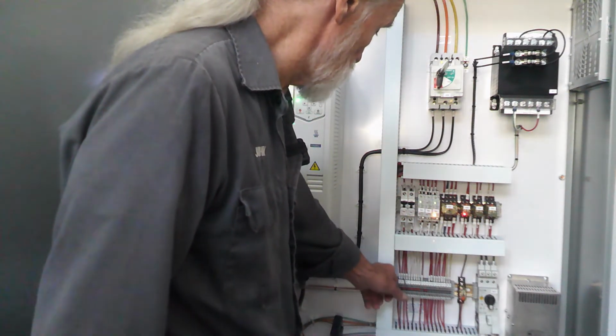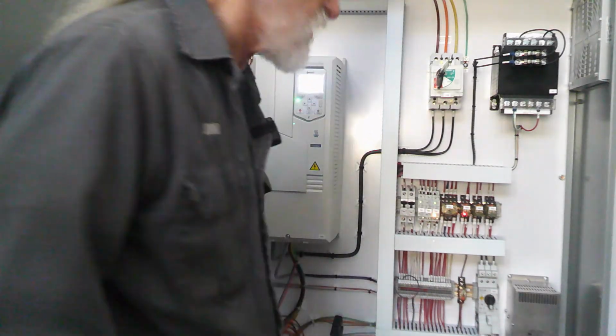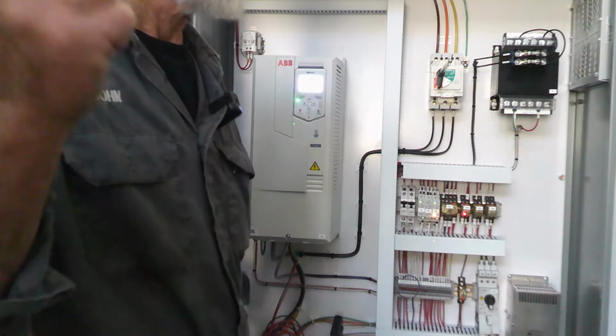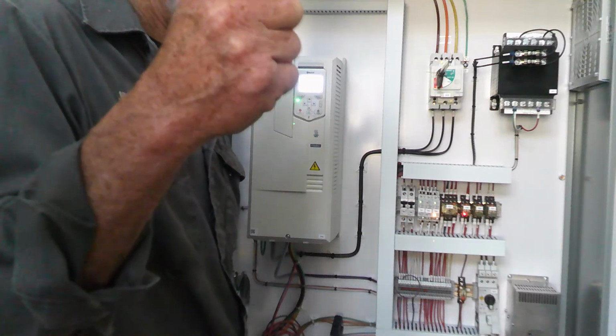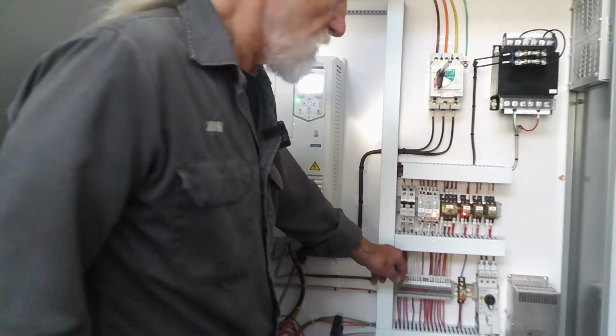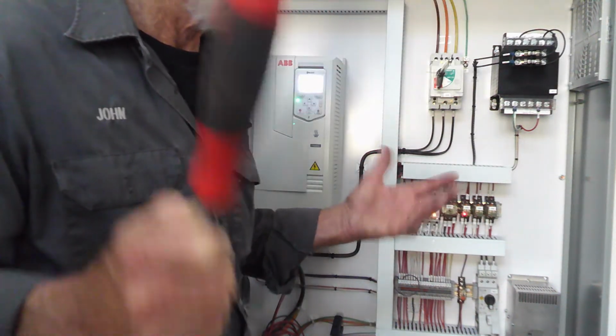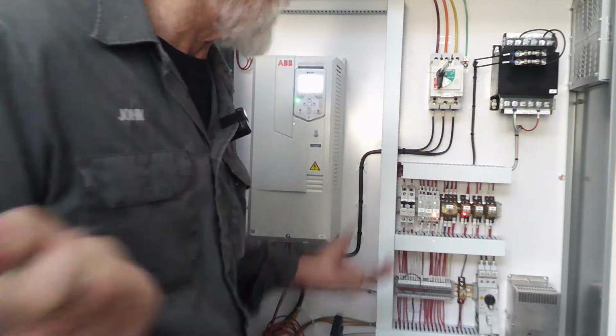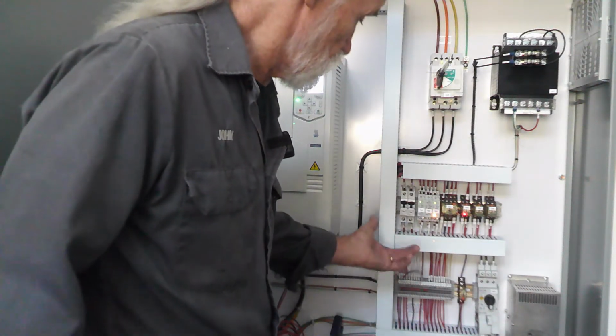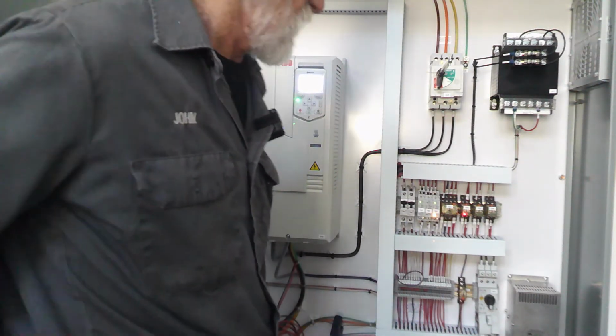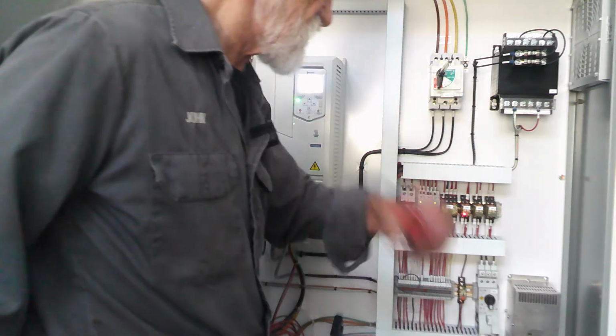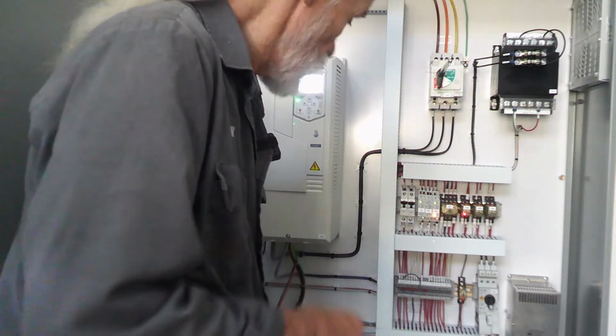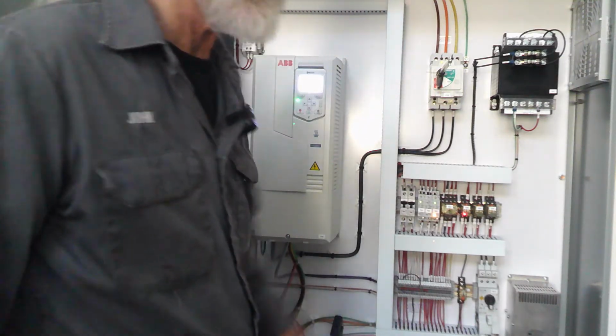This, I think I remember what this is. This was bypassing the non-return valve because they hadn't mounted the sensors, among other things, so that had to be allowing the unit to run. Since it wasn't put together yet, this jumper has nothing to do with those current sensing switches, I thought, because I'll do that one myself. I make it big so somebody later can see this is a jumper. But I remember now, that bypasses that valve, so I could actually pull that out. For the time being I won't, because we can't test that anyway.